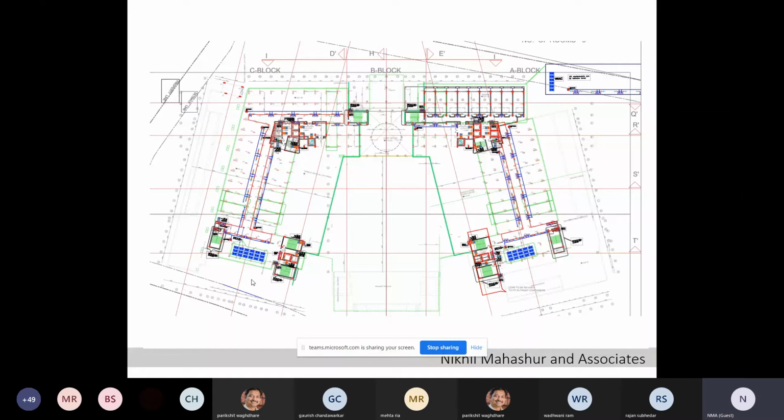So if you have a service floor between the hotel rooms and the ballroom or the restaurant, you can actually have the ring main in the service floor. Either that, you can have it on the terrace, or you could also increase the height of your ground floor and have it in the ceiling of your restaurant, etc. Most people will tell you that that's not the ideal situation, but really in practice, we've done it a lot of times. Not a problem at all. We give trapdoors, and it can be easily accessed, and never a problem with leakage, etc.